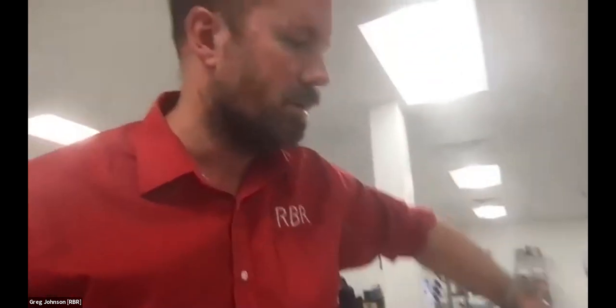Most of the tanks are empty at this time of day because we perform all of the calibrations overnight. We can set up the instruments, load them into carousels, and then drop them in. I can find, for instance, under here, a calibration carousel. This will hold 20 of our compact instruments, and we lower that into the tank, press a button, and come back in the morning to retrieve the instruments.